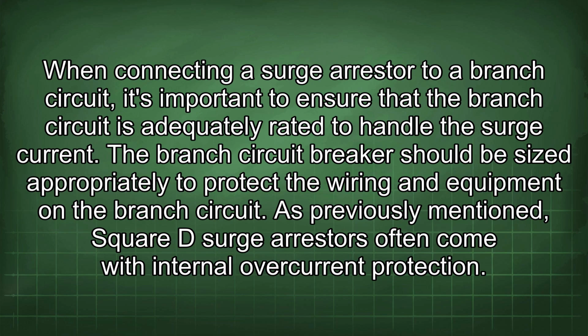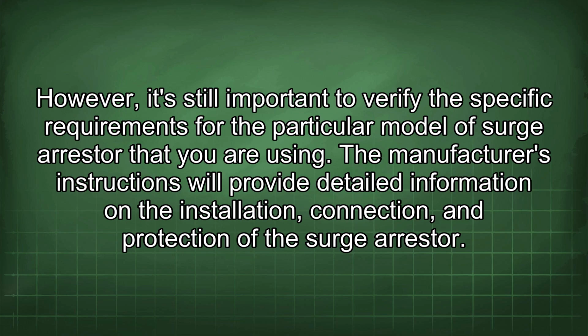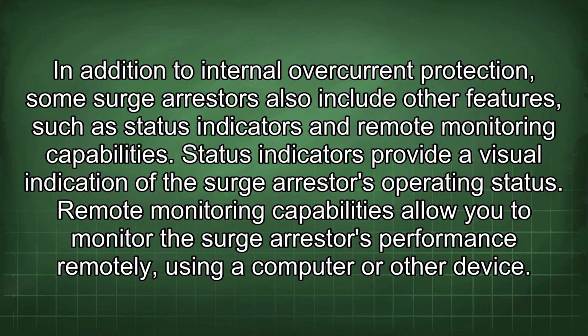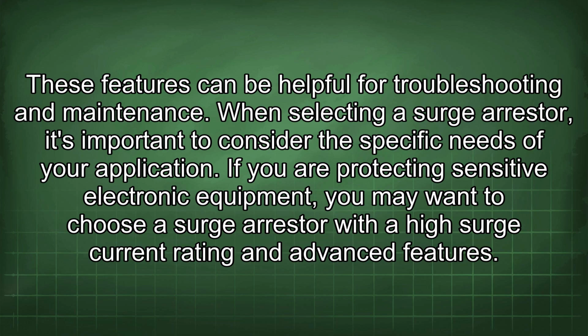As previously mentioned, Square D surge arrestors often come with internal overcurrent protection. However, it's still important to verify the specific requirements for the particular model of surge arrestor that you are using. The manufacturer's instructions will provide detailed information on the installation, connection, and protection of the surge arrestor. In addition to internal overcurrent protection, some surge arrestors also include other features such as status indicators and remote monitoring capabilities. Status indicators provide a visual indication of the surge arrestor's operating status. Remote monitoring capabilities allow you to monitor the surge arrestor's performance remotely, using a computer or other device. These features can be helpful for troubleshooting and maintenance.